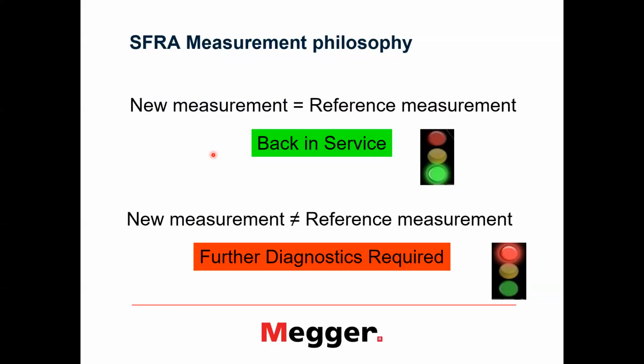However, the problems start when we don't have this agreement and the new measurement is not the same as the reference one. So then we start to dig deeper and investigate what has happened, starting with setup analysis, and then if that turns out good, we go and analyze what has happened with the transformer itself.